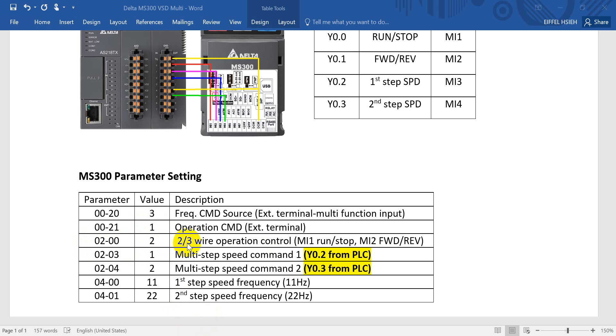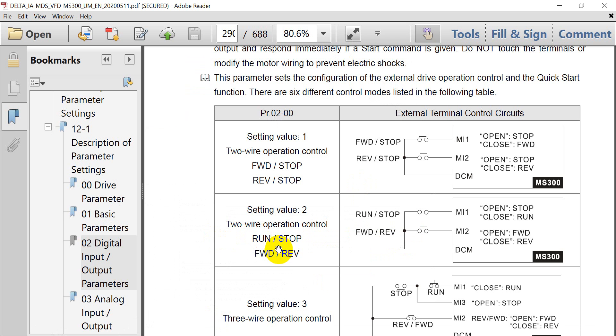Parameter 02-00 is set to 2, meaning two-wire operation control: MI1 means run and stop, MI2 means forward/reverse as mentioned earlier. For more detail, check the user manual. Value 2 means MI1 closed = run, open = stop; MI2 closed = reverse, open = forward.